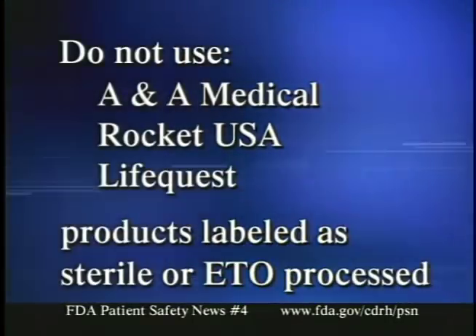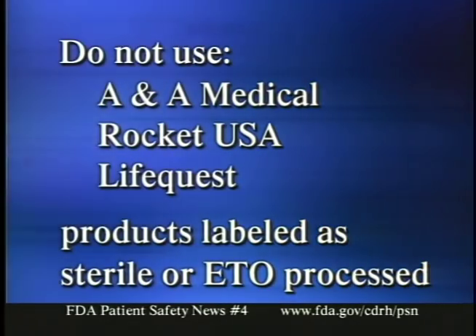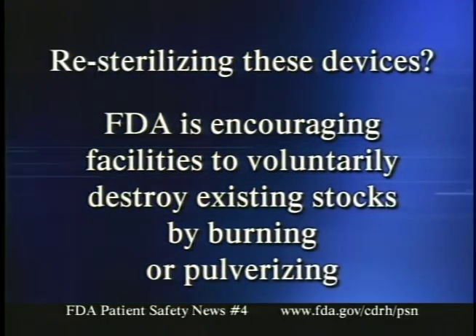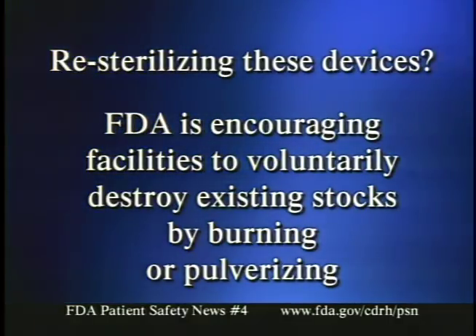Here's how to handle this recall in your facility. First, do not use A & A Medical, Rocket USA, or LifeQuest products that are labeled as sterile or ethylene oxide processed. Second, periodically consult our website for updates on this recall. Since the last broadcast, people have asked about re-sterilizing these devices on site — you should not attempt to do this. Instead, FDA is encouraging facilities to voluntarily destroy existing stocks by burning or pulverizing them.